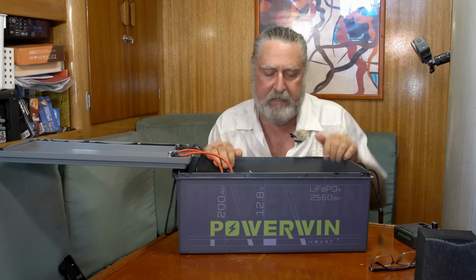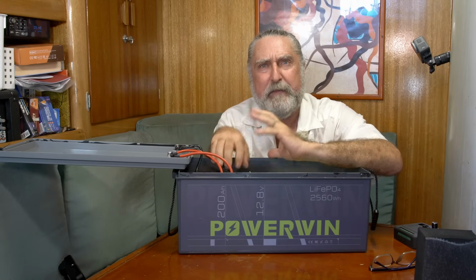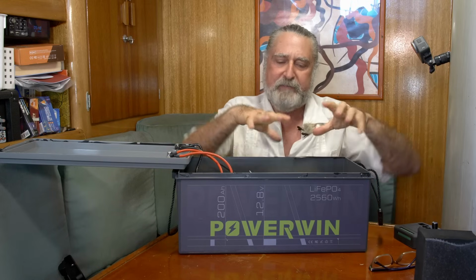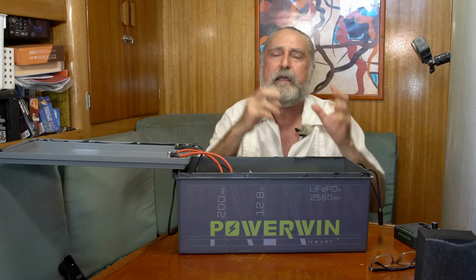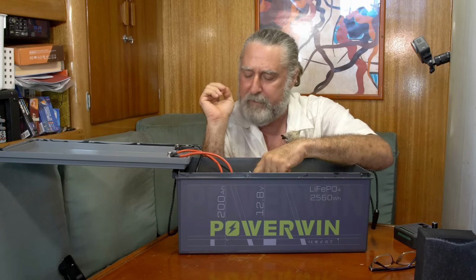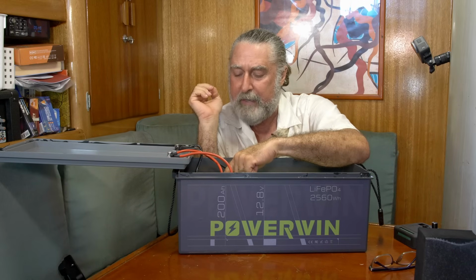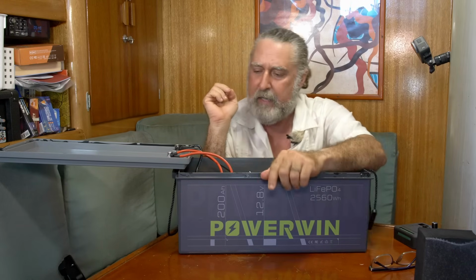Well, that's disappointing. In their specifications, they don't expressly say how many amps the BMS can pass, but they strongly imply it's a 200 amp BMS. It's a 200 amp hour battery - that's different, that's how much capacity it has. It can produce anything you want to multiply, like 200 amps for 1 hour, for example. Except this one couldn't, because the BMS is plainly labeled as a 100 amp BMS.